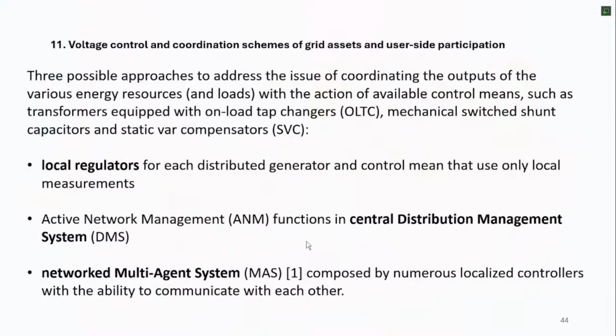And then there is, on the other side, the so-called active network management function of the central distribution management system. So a centralized optimization control that collects all the information from the networks, does the optimization as in the first part of this morning, and sends all the signals. There is also another idea, that is the networked multi-agent system. The controllers in each of the photovoltaic units make decisions not completely autonomously, but exchanging some coordinating information with the controllers of the other photovoltaic units connected in the same feeders, and also the controllers of the distribution transformers and so on. Some kind of distributed controller.